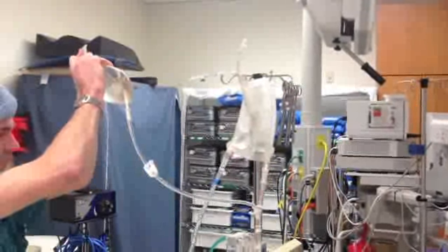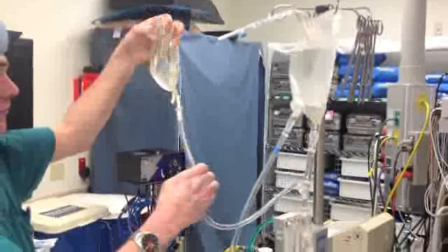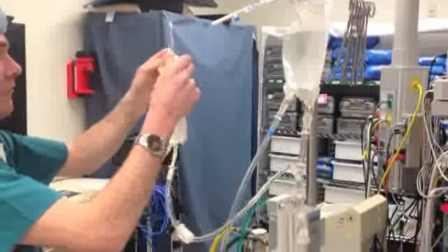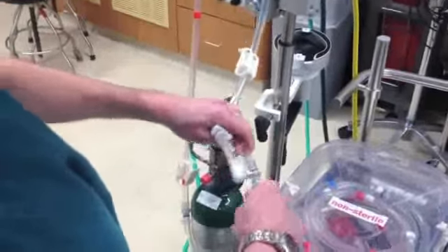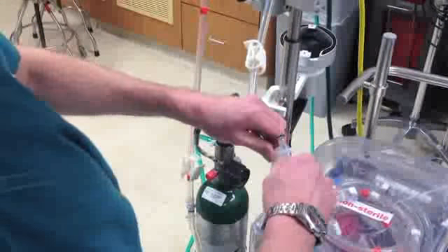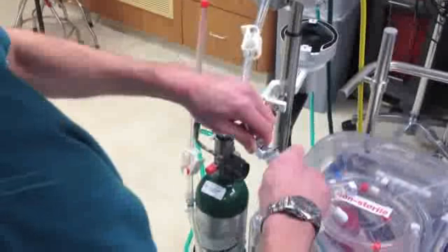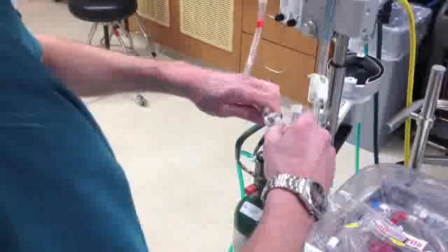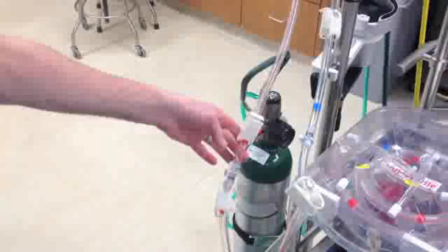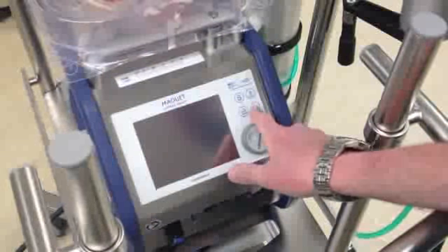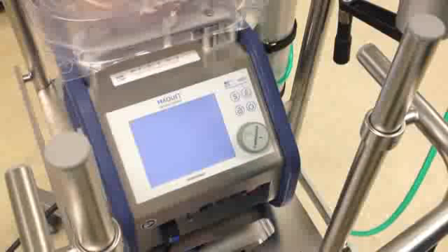This here is your fluids connected to the priming line. You got to squeeze in 1.5 liters. Literally, you have to squeeze it in and then clamp off the priming line. Then you'll disconnect the quick connect adapters to the table set lines and the priming lines, and you'll connect the blue to the blue and the red to the red, so this way the priming lines are now connected to the table tray lines. You'll go back around to the front of the console and turn it on.